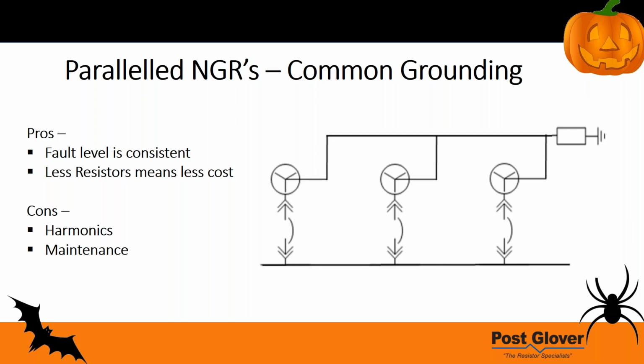But it's not only the harmonics that are an issue, because everything's tied together. Let's say you take out that leftmost generator—since the neutrals are tied together, if there's no fault condition, you're good to go. But if you get a fault condition, you're going to have some issues if you're trying to maintenance that generator. So you're in a situation where the maintenance guys may think the generator is offline, but not really, because you get that fault and you're still live. So really the only option in this scenario is to maintenance it while it's completely offline.